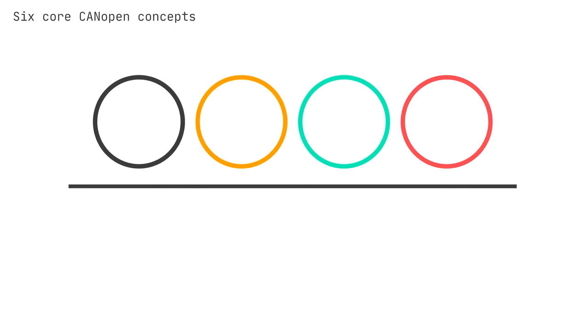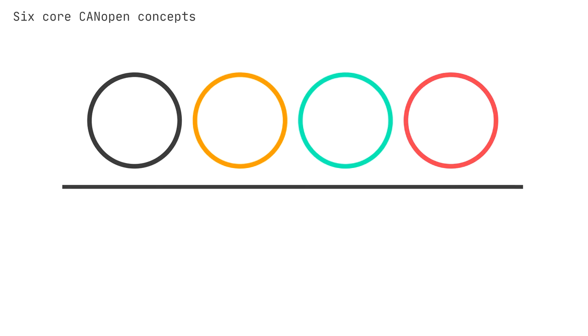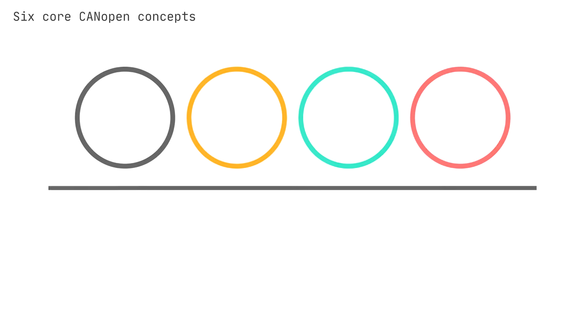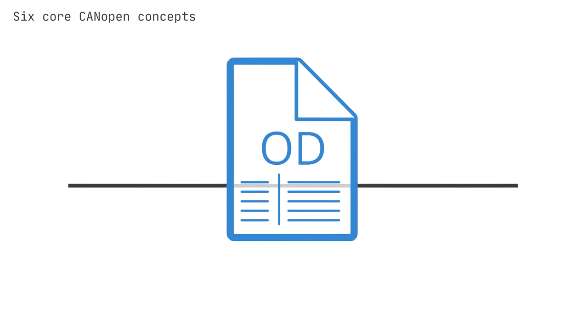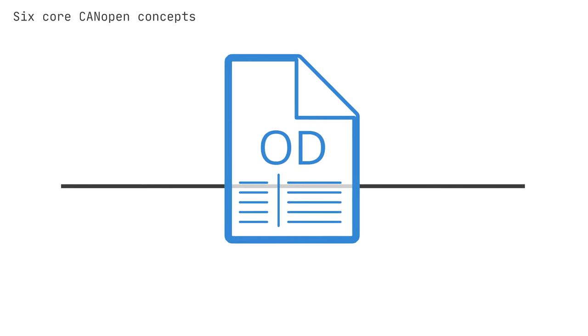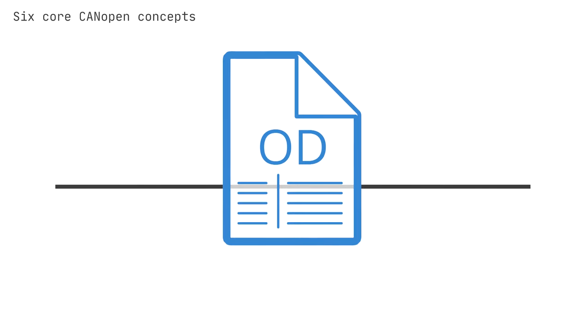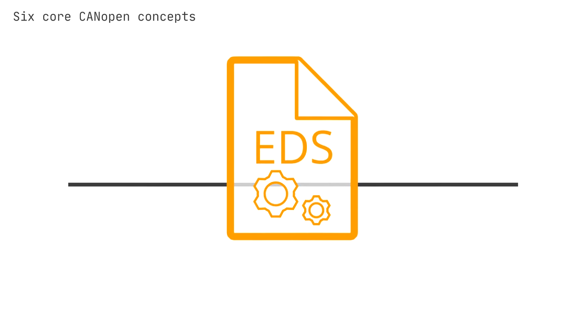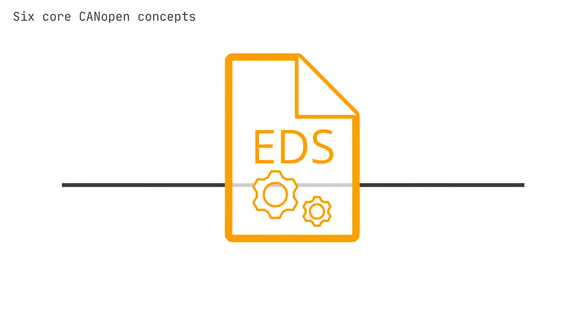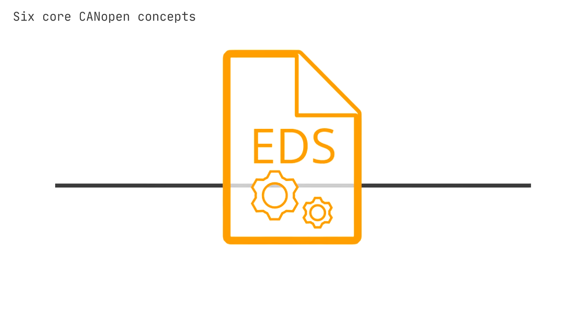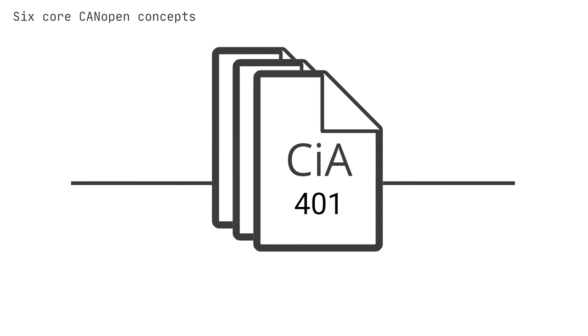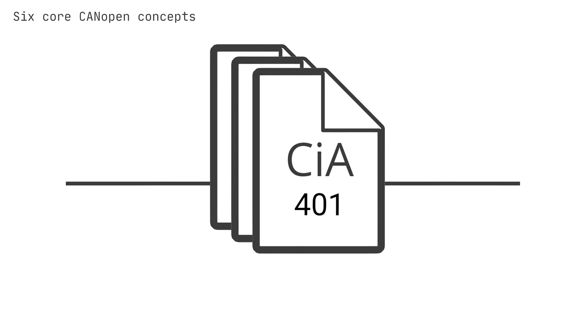Number three: device states — a device supports different states, and a master node can change the state of a slave node, for example resetting it. Number four: object dictionary — each device has an OD with entries that specify, for example, the device config, and it can be accessed via SDOs. Number five: electronic datasheet — the EDS is a standard file format for OD entries, allowing service tools to update devices. Number six: device profiles — standards describe, for example, IO modules (CiA 401) and motion control (CiA 402), for vendor independence.